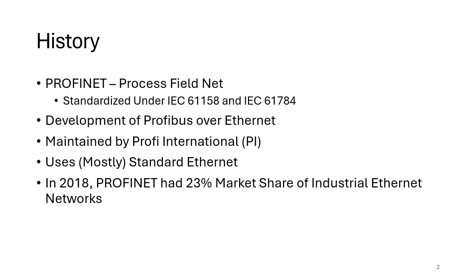Now, PROFINET was originally called Process Field Net or Process Field Network, and it was standardized under two standards, IEC 61158 and IEC 61784. PROFINET these days is maintained by Profi International, or the PI organization, and as I mentioned, it's mostly standard Ethernet. You can certainly run PROFINET on purely standard Ethernet. Some functions do need specialized networking equipment, and again, I'll cover that a bit later.